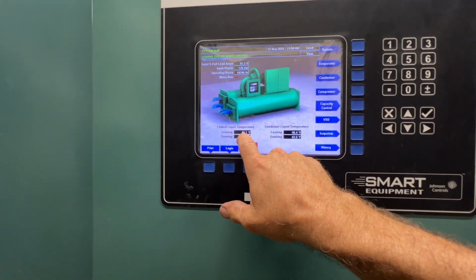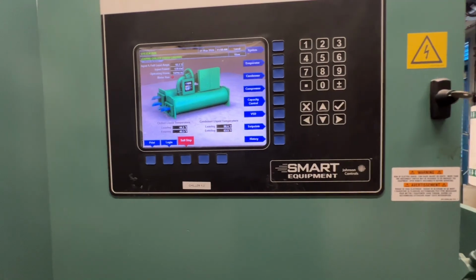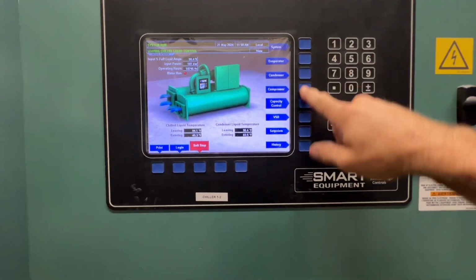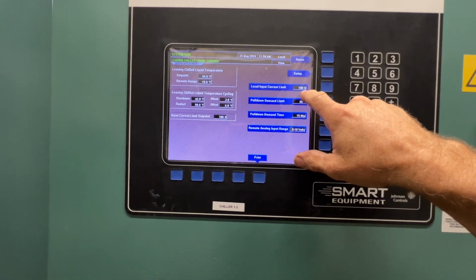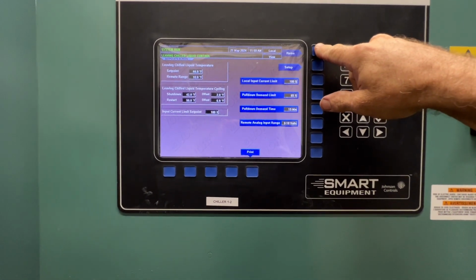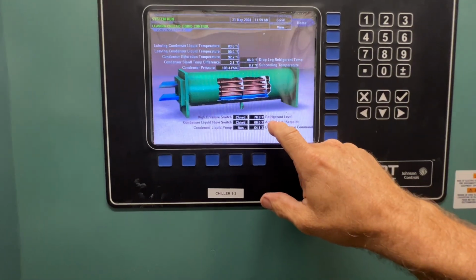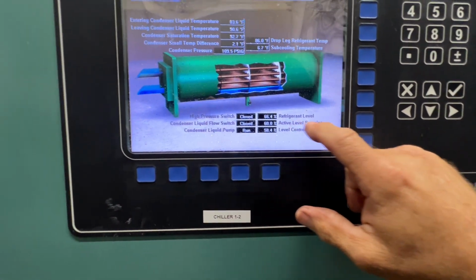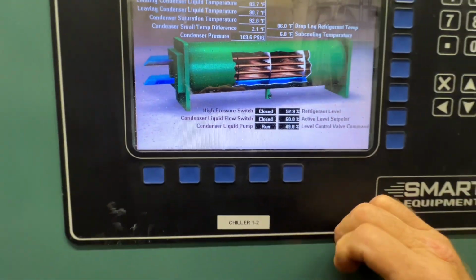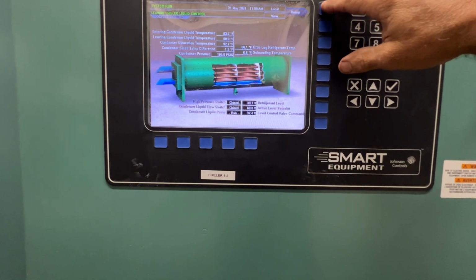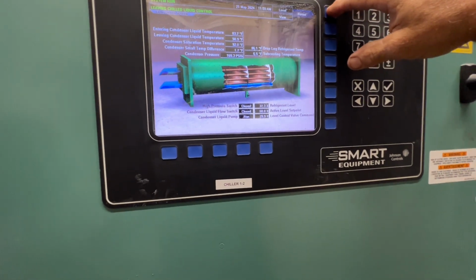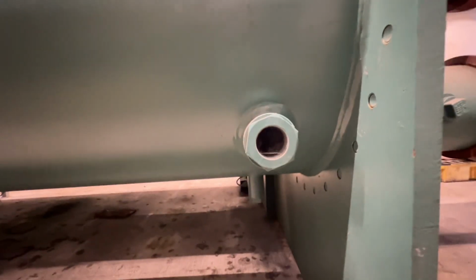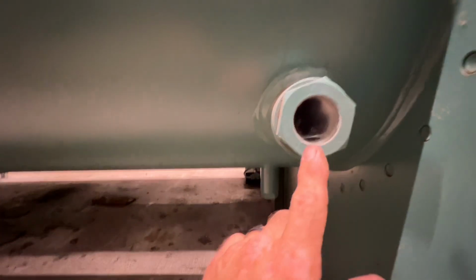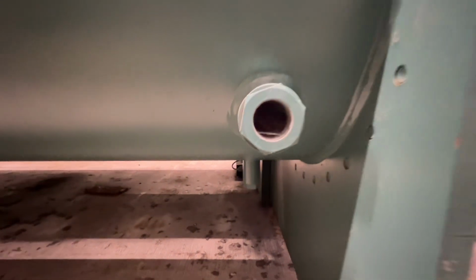Currently we have 44 degrees leaving, 49 entering, which kind of corresponds with our chiller 1. He raised this one from 90 to 100%. And what else did he do? Lowered the refrigerant level. The set point was at 80% on this one. He lowered it to 60%, but also believes that the level sensor may need to be calibrated. It's kind of jumping all over the place. I haven't gotten a loss of seal warning on this one yet for the subcooler seal, but I imagine if it runs too much more like that, I may get it.